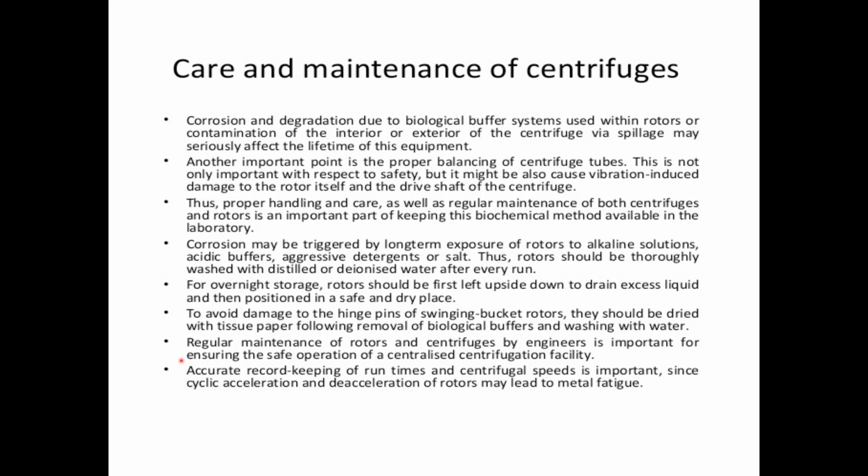It is important that the laboratory invests into regular maintenance and service contracts for rotors and centrifuge. Engineers come frequently to the labs. They test the rotors, they test the centrifuges, because rotors, when they reach a certain age, have a bit of corrosion, and when they corrode, then the weight is not equally distributed anymore. And these little weight imbalances cause tremendous problems for the machines when you think about the acceleration of 100,000 G, for example.